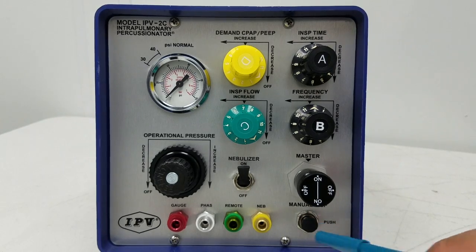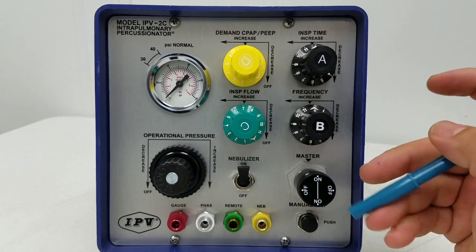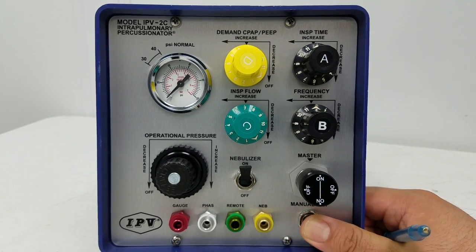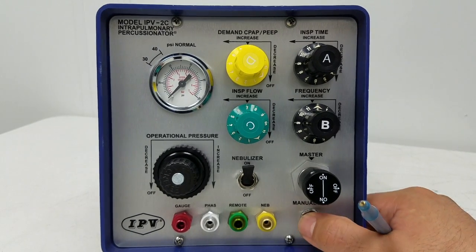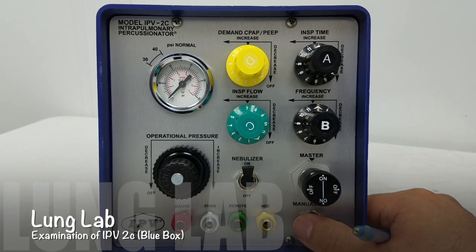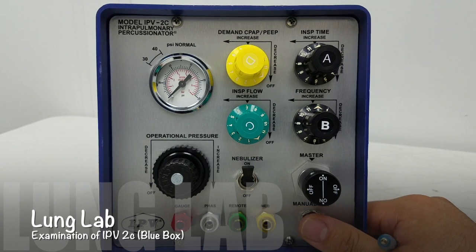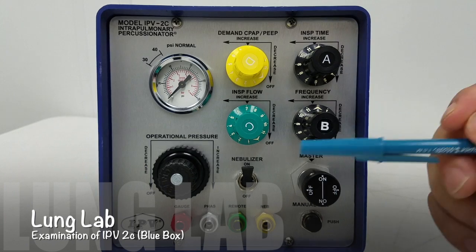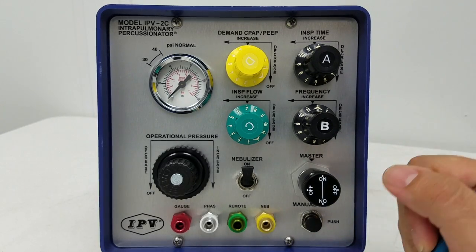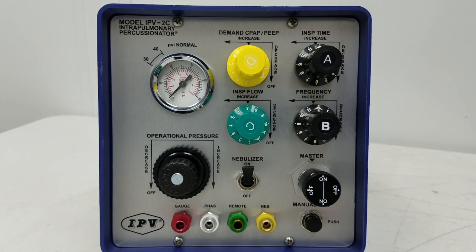You have a manual inspiration push button — I tend not to use this button. You can create a manual breath with it, but there's no limitation on it, so if you're holding it too long it's possible to cause barotrauma. It takes skill from the therapist. I can effectively recruit by utilizing my inspiratory flow and frequency much better than just giving them a rush of flow — that's a preference from my own experience. Thank you for watching Lung Lab, your host Louis Rueda — this is part one of our new series.